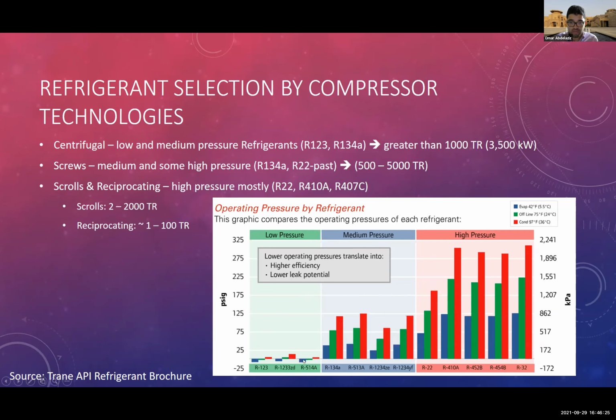For low pressure, we don't have too many options. So there is the HFO R1233ZD, and you can see the pressures are quite low. If you look at it in PSIG, the evaporating pressure of R123 is subatmospheric. 1233ZD is again a little bit above atmospheric, and condensing pressure is always above atmospheric. And you can see for medium pressures, you are at much higher pressures. High pressure is almost double that of the medium pressure.